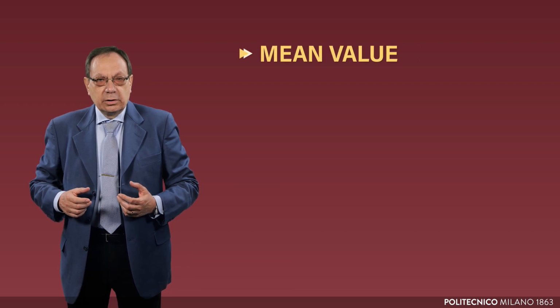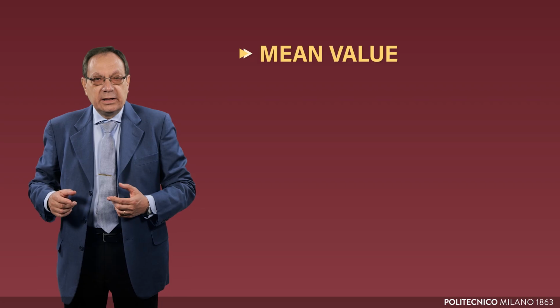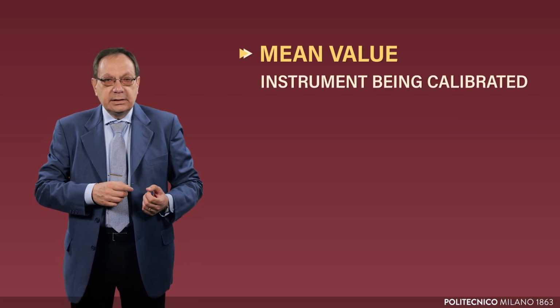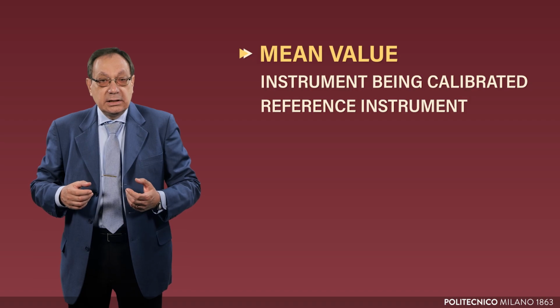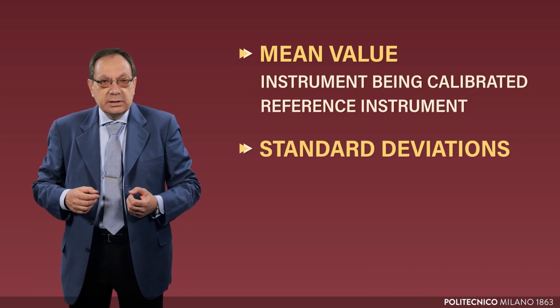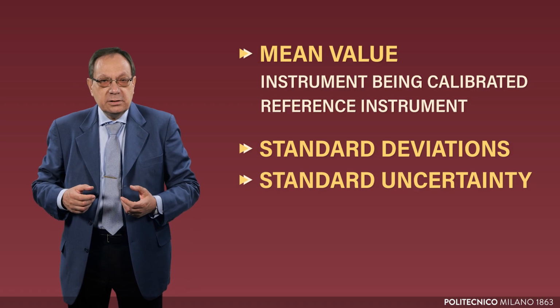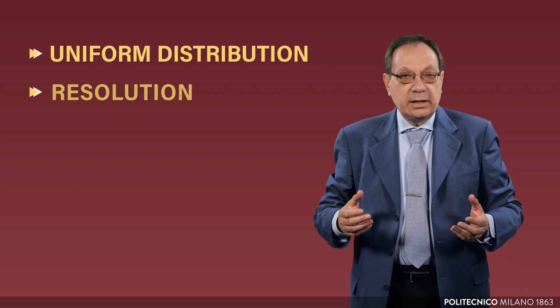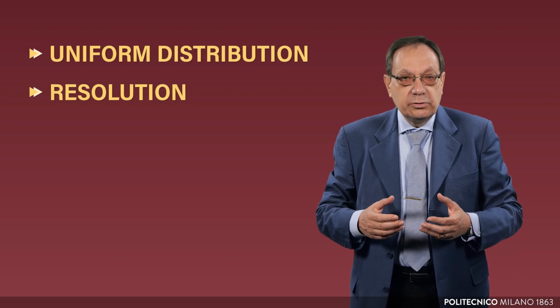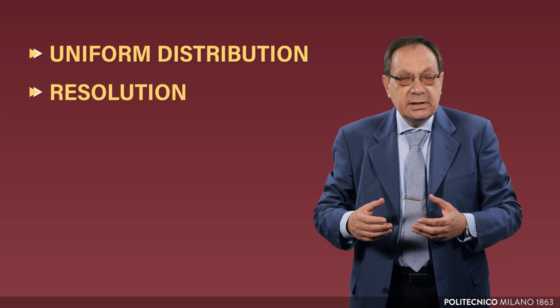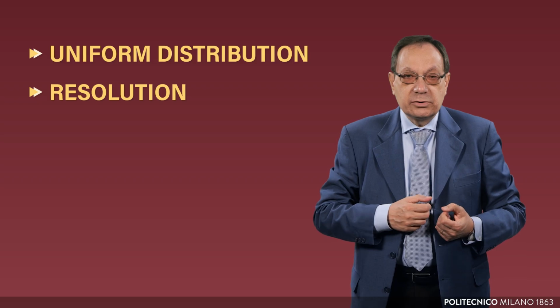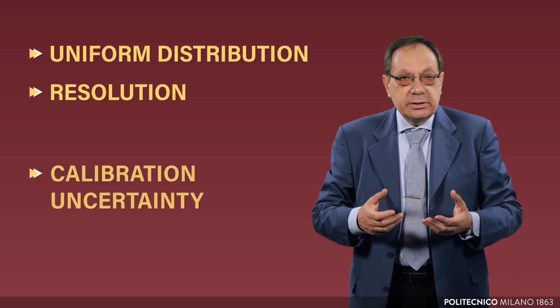At the end of the acquisition, it computes the mean value of the 30 recorded values for each of the set voltage values, both for the instrument being calibrated and for the reference instrument, as well as the corresponding standard deviations from which it derives the standard uncertainty value to be associated with the mean values. The program then assesses the standard uncertainty contribution given by the resolution of the 2 instruments, assuming a uniform distribution of the resolution error, and combines the uncertainty contributions of the instrument under calibration and the reference instrument quadratically, as shown in the previous video, to determine the calibration uncertainty.